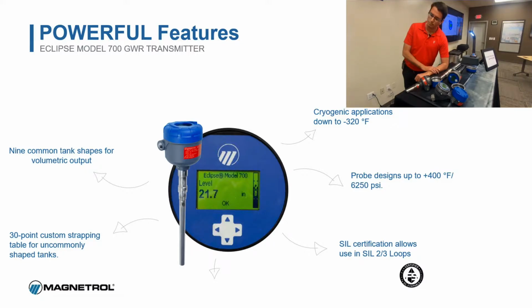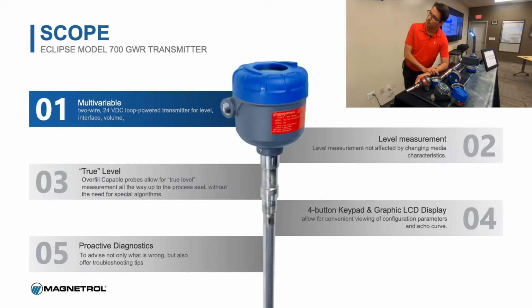It's all the 700 features. We have 9 common tank shapes for the volumetric output. So if you want to extrapolate volume from the level measurement, we can help you there. We also have a 30-point custom strapping table for uncommonly shaped tanks, also for changing level to volume. We've got it available for cryogenic applications. As I mentioned before, the probe designs go up to 400 degrees and 6250 PSI, and we have the SIL certification.